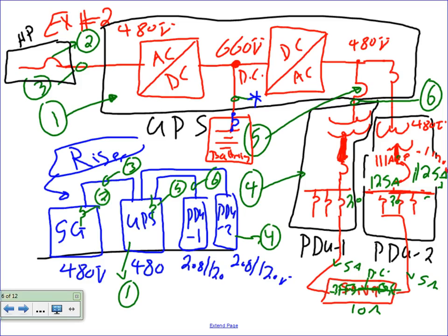Now, here's what happened. Now this one drops down, and this one doubles to 10 amps. Nothing will happen. Now, in my example, if the UPS goes down, I am dead. But what they do in a real project, guys, is they take this circuit breaker here and feed it from a completely different UPS system. So they feed each PDU from a different UPS. Then if the UPS goes to hell on this side, you still have another UPS.